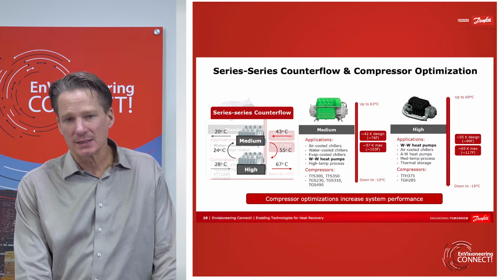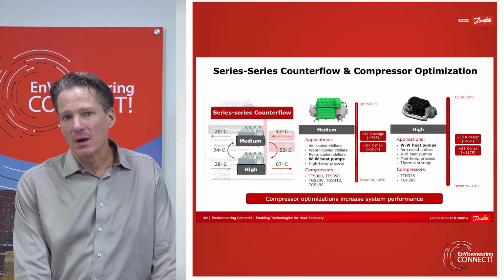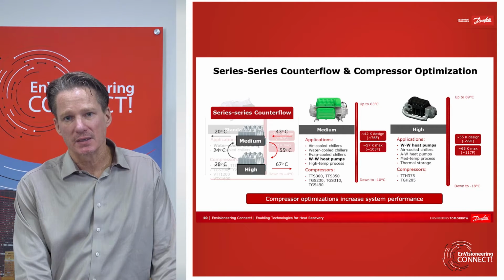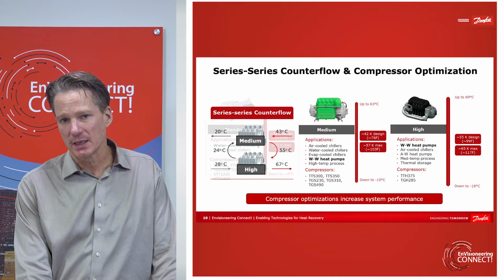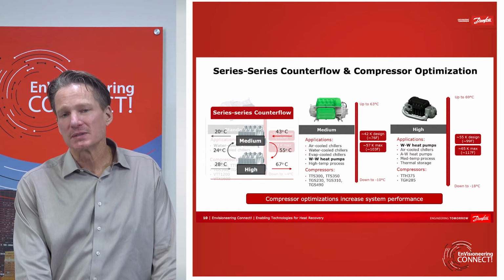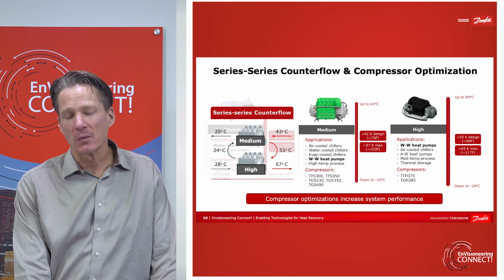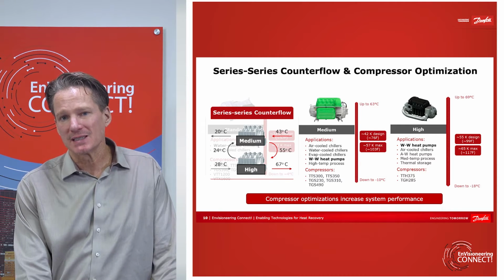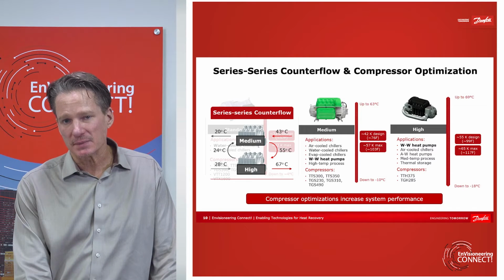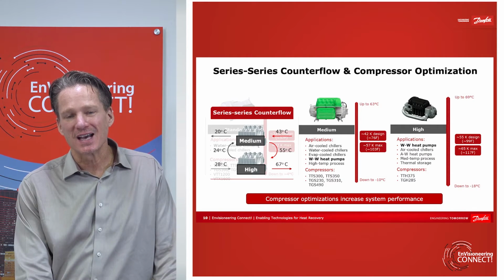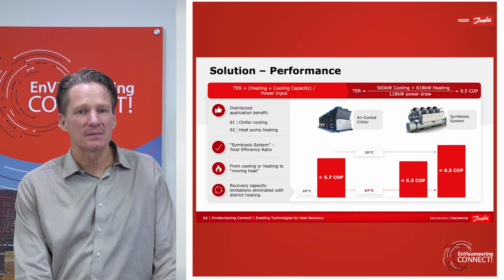So the individual compressors utilized, and in this case, of course, it's the Turbocor compressors on a water-to-water heat pump, are applied on a first stage and then a second stage water-to-water heat pump system, as shown here on the left-hand side. Each one of those uses a different compressor optimization because of the corresponding work that it has to do. So the low stage and the high stage have different compressor optimizations because that allows you to increase the overall efficiency of the water-to-water heat pump system. In this case, the low stage uses a medium lift optimized compressor design, and the high stage uses a high lift optimized compressor design. And this shows it in symbiosis efficiency terms.